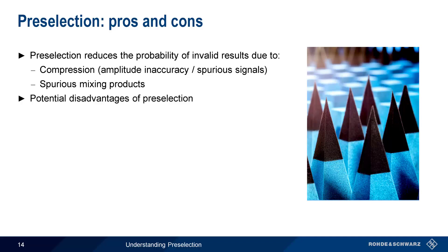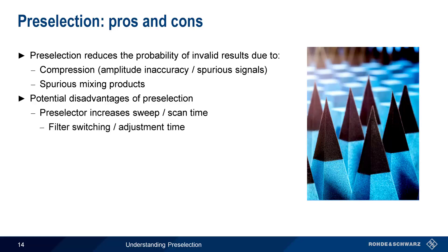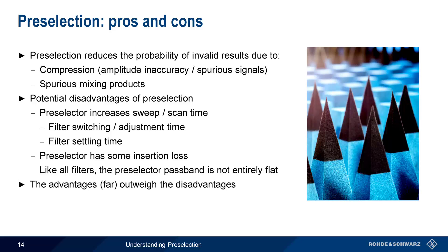So what are the pros and cons of using preselection? The main advantage is that it reduces the probability of invalid results due to compression and/or the creation of spurious mixing products. There are, however, a couple of things to keep in mind. First, a preselector can increase the time needed to perform a sweep or scan, due to the time needed to switch between filters in a filter bank, or to adjust a tunable filter, as well as the settling time needed for the filter. Less serious considerations include any insertion loss caused by the preselector, and the fact that the passband in preselection filters will not be entirely flat. That said, in the vast majority of cases, the advantages of preselection far outweigh the potential disadvantages.